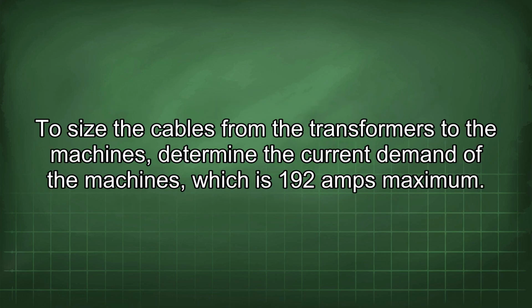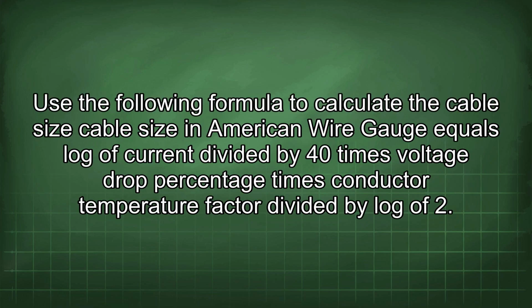To size the cables from the transformers to the machines, determine the current demand of the machines, which is 192 amps maximum. Use the following formula to calculate the cable size. Cable size in American wire gauge equals log of current divided by 40 times voltage drop percentage times conductor temperature factor, divided by log of 2.